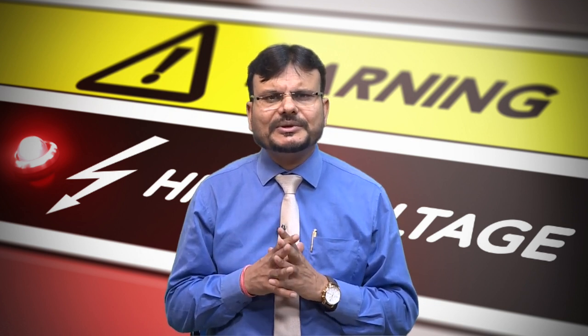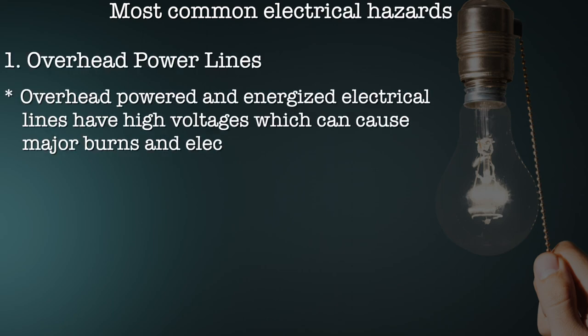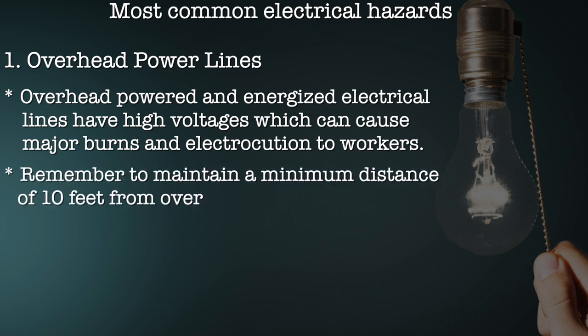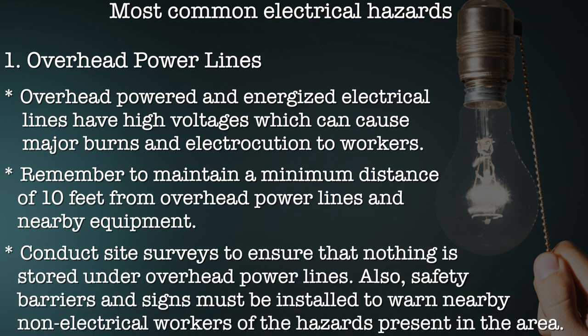Here are some of the most common electrical hazards in the workplace and tips on how these risks can be mitigated. The first one is overhead power lines. Overhead energized electrical lines have high voltage which can cause major burns and electrocution to workers. Remember to maintain a minimum distance of 10 feet from overhead power lines and nearby equipment. Conduct site surveys to ensure nothing is stored under overhead power lines.